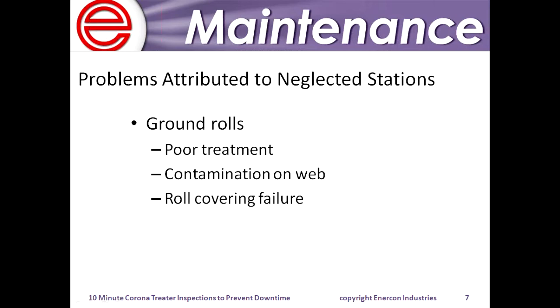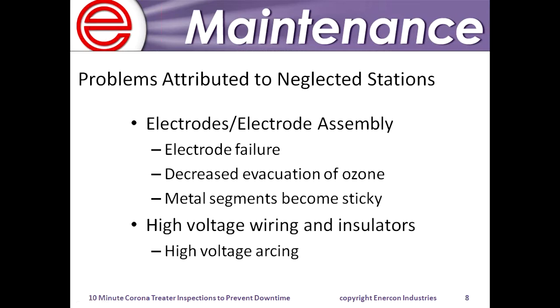Anytime you have carbon or dirt or some organic material that's just kind of sitting and hanging out, where you're exposing that to high voltage, 10,000 volts, that can certainly become conductive, carbonized, and lead to localized heating and shorten the life of things. So that's definitely something to keep in mind.